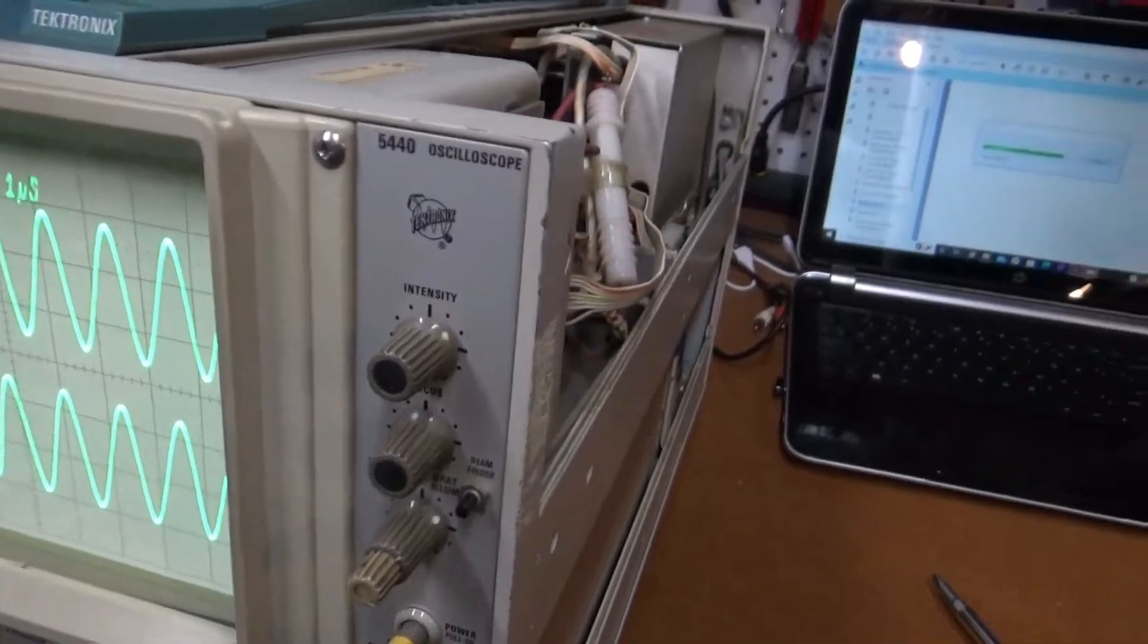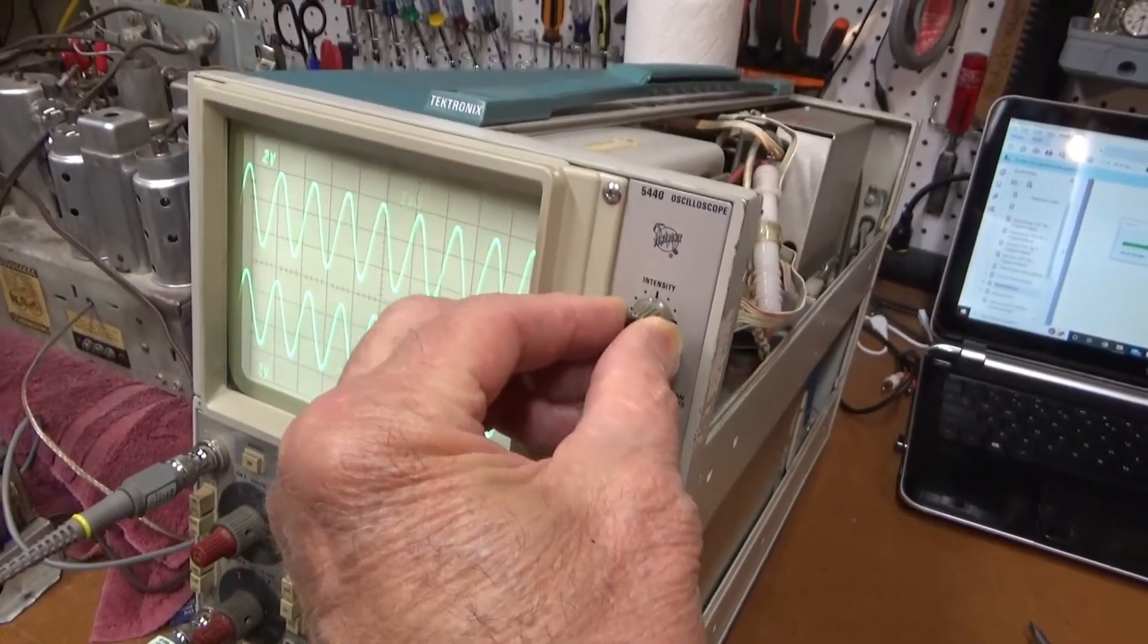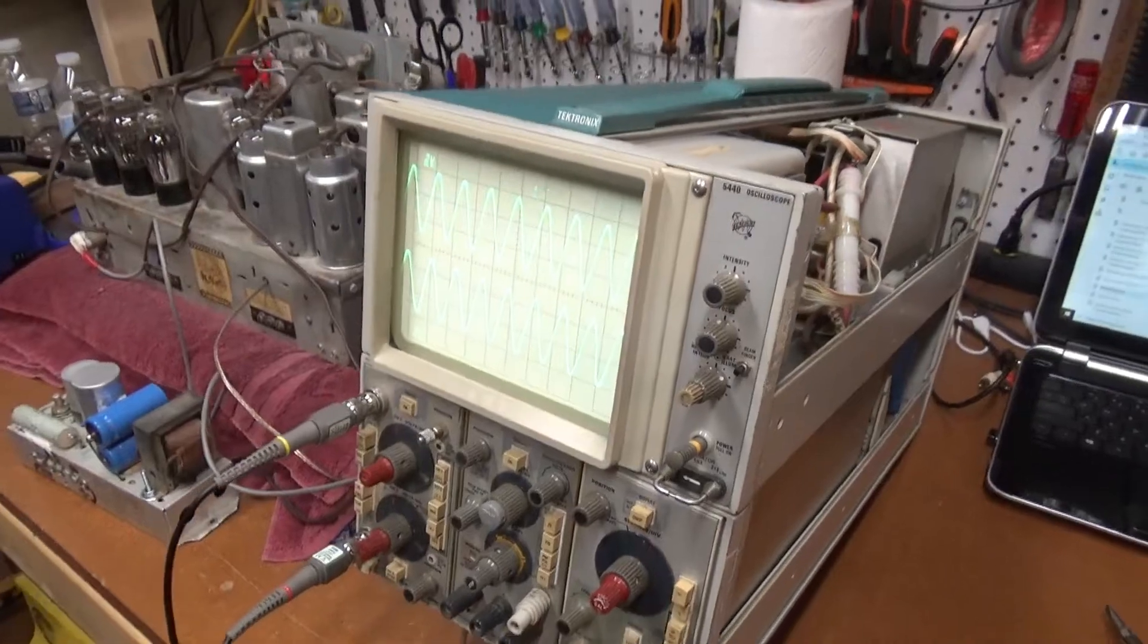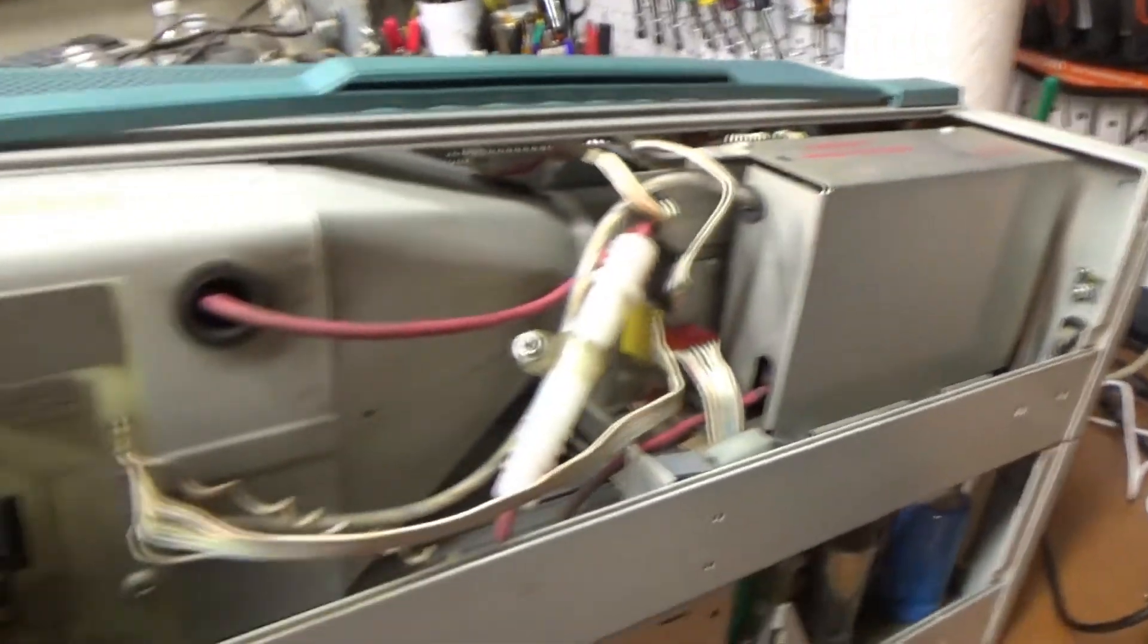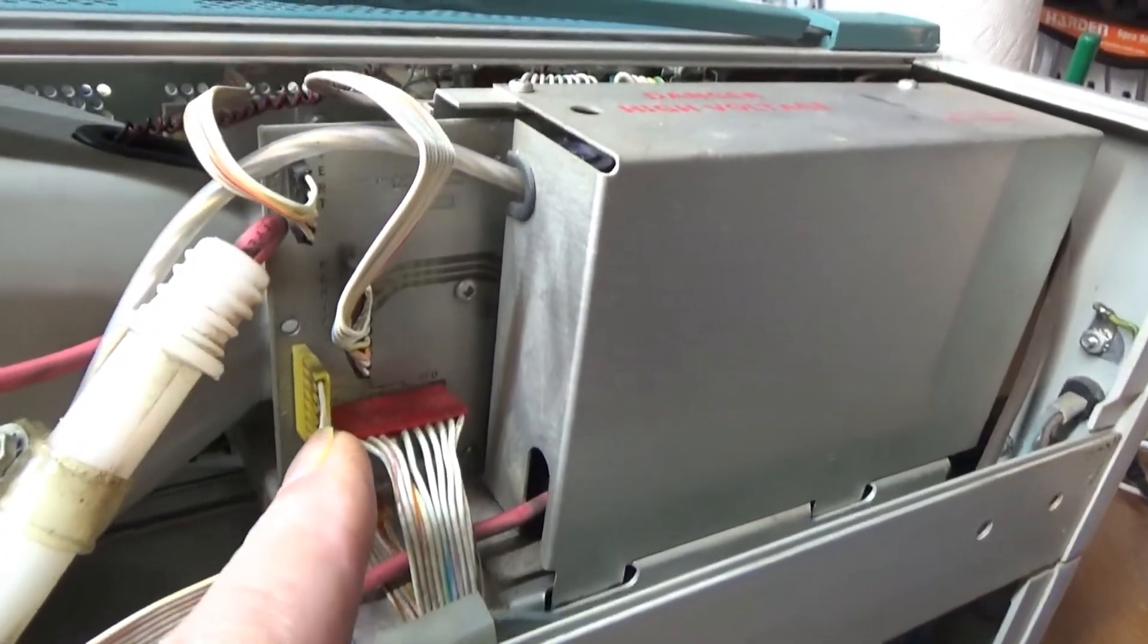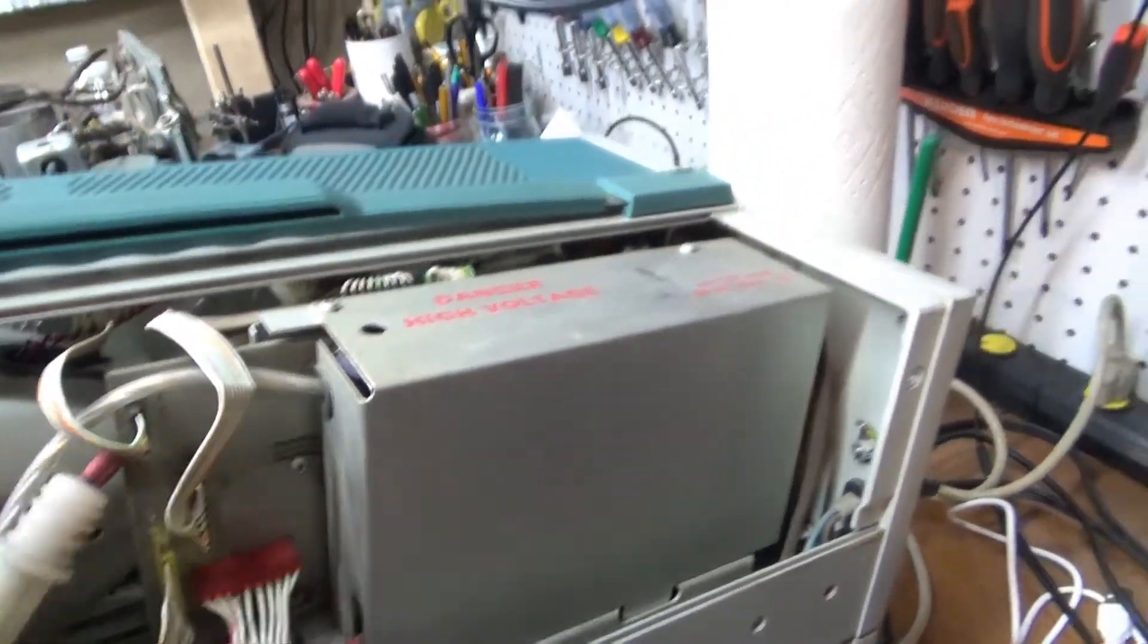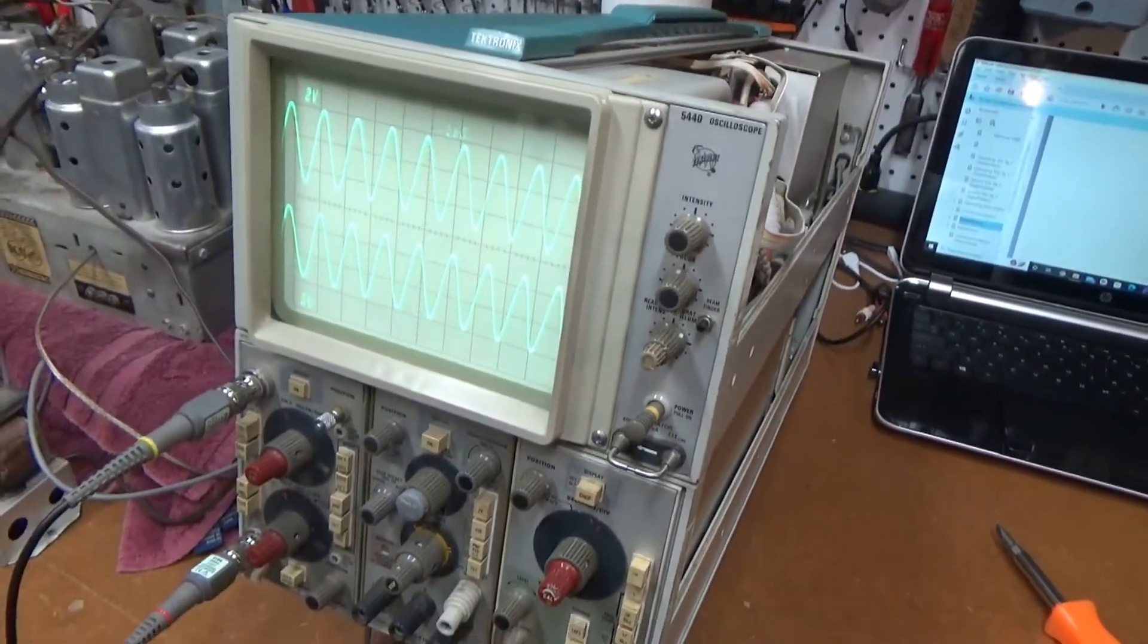This is Tektronix Model 5440 oscilloscope. Seems to be working properly. The intensity isn't varying anymore even if I jiggle it and hit it. So I think I've gotten the bad connections all straightened out. I just cleaned up the connections on the back of the CRT and also from this little board which does the intensity controls, this little ribbon cable. I think that would make a bad connection also. So I treated that with the deoxid and the CRT connection with the deoxid. And I can't get it to fail now. So I think we're good.